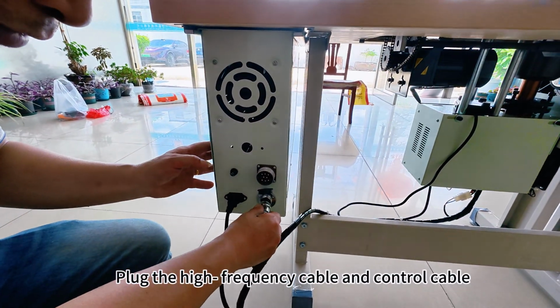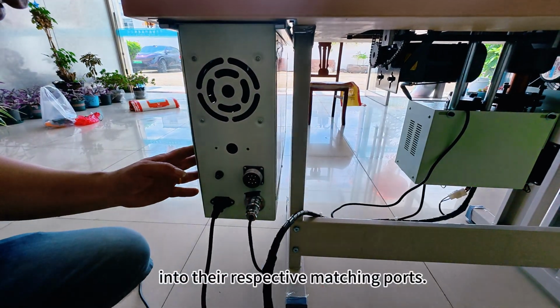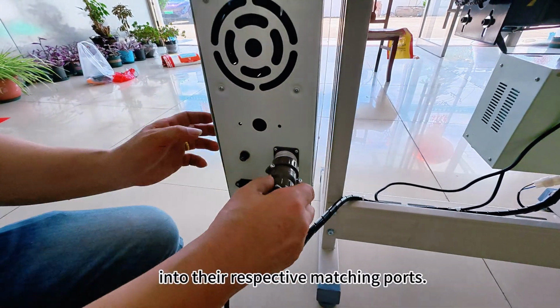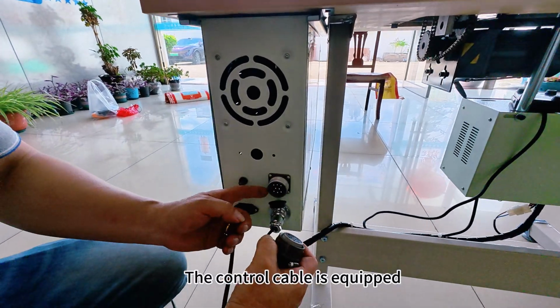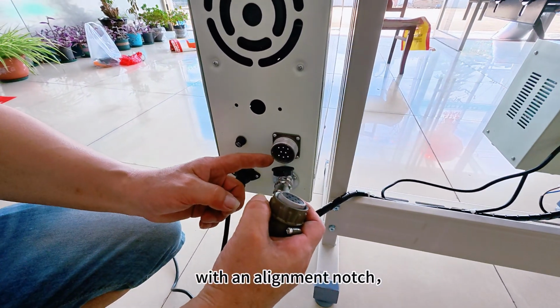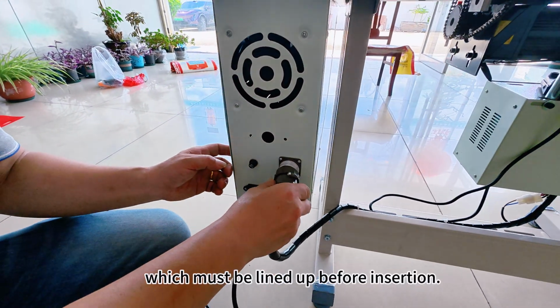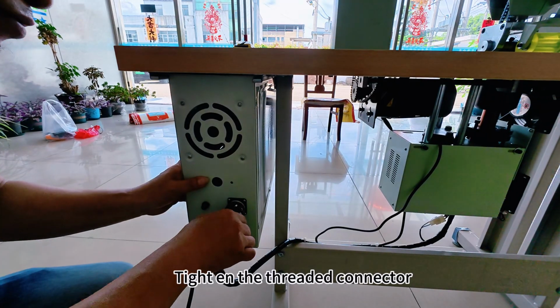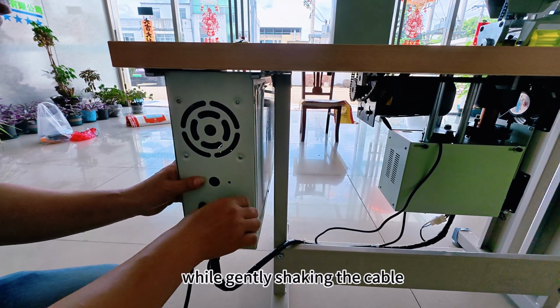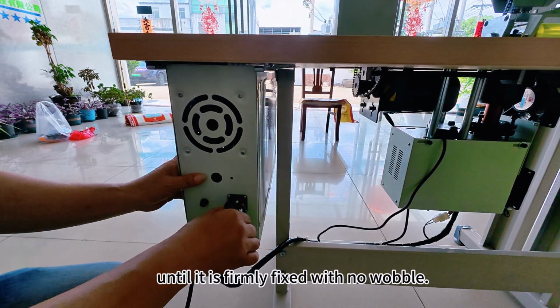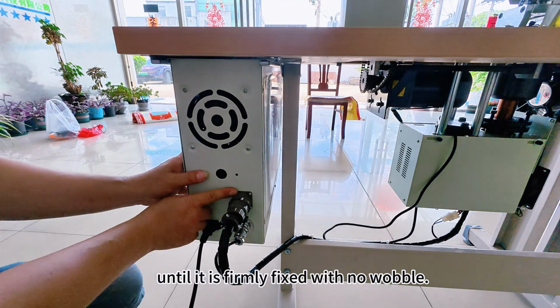Plug the high-frequency cable and control cable into their respective matching ports. The control cable is equipped with an alignment notch, which must be lined up before insertion. Tighten the threaded connector while gently shaking the cable until it is firmly fixed with no wobble.